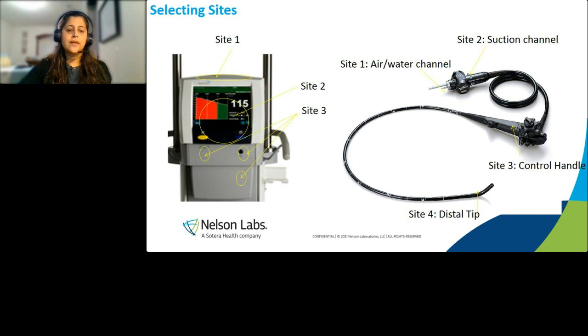Those are different. And then when we get non-critical devices or even semi-critical devices like a flexible endoscope, we're not testing the entire device, but we're selecting test sites for it. Of course, with the flexible endoscopes, you guys have heard there's a lot to worry about. And so we do challenge the endoscopes quite heavily. And they have good size channels that we do test. I mean, we have the instrument suction channel, air water channel, control handle, distal tip. If it's got an auxiliary water channel, we would do that. So all the channels would be challenged, including the exterior sites that are mostly handled.